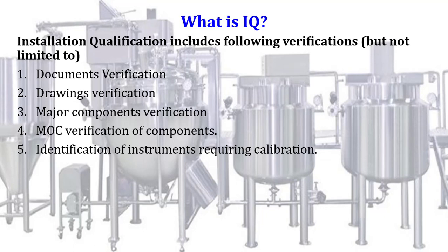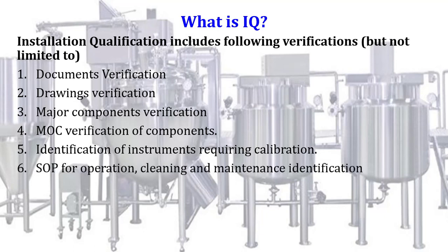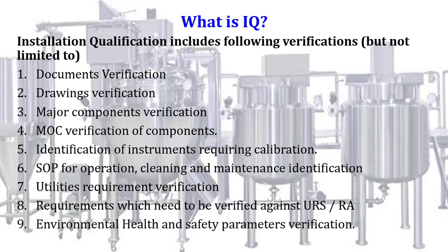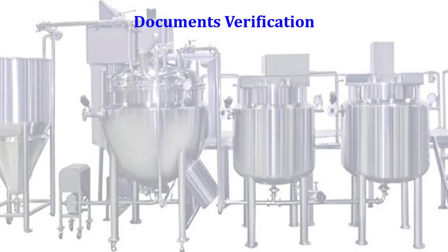Further verifications include: identification of instruments requiring calibration, SOPs for operation, cleaning and maintenance identification, utilities requirement verification, requirements which need to be verified against URS or risk assessment, and environmental health and safety parameters verification. All these nine points need to be verified during installation qualification. These are not limited — you can verify other parameters based on equipment requirements.